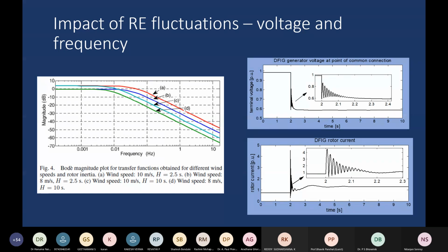So here we are talking about a doubly fed induction generator, which is the generator that is usually connected to the wind turbine at high power level. So a typical 5 megawatt wind turbine would generally be connected to a doubly fed induction generator. Smaller size turbines are connected to fixed speed generators. The benefit of using a doubly fed induction generator is that it allows you to operate at different speeds. Thereby you can actually extract more and more power from the varying wind speeds.